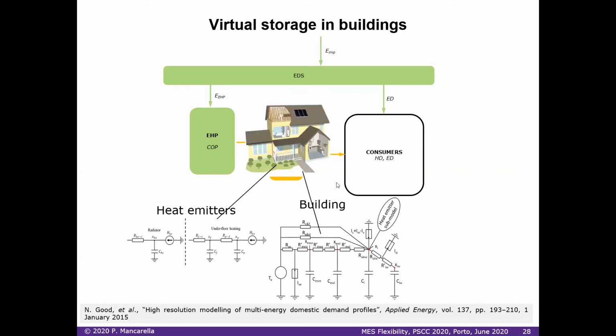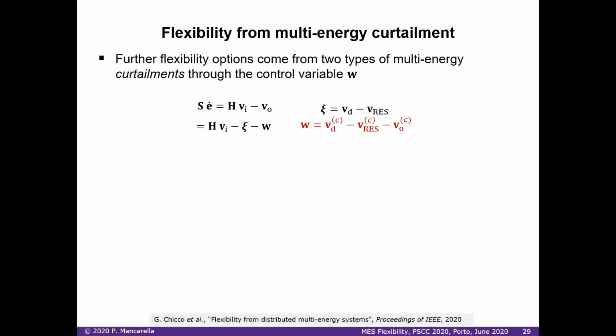And if I substitute this thermal energy store here with a building, and then I describe the building with its multiple storage components that would be primarily coming from thermal inertia in the building, again, I have an equivalent thermal store, but in this case, it's the physics of the building that is providing that. This is the idea of virtual storage coming from buildings. In fact, this virtual storage really can operate as a virtual battery, as we will see.